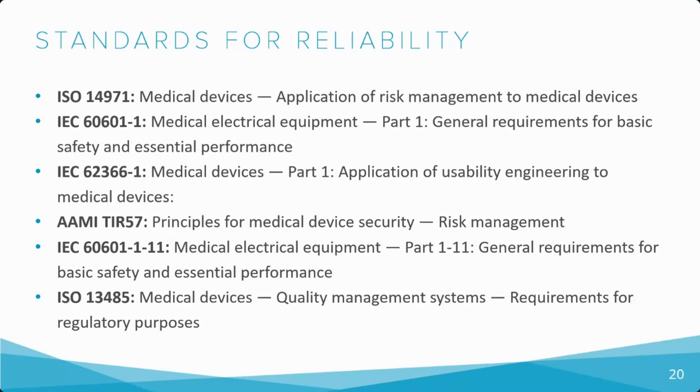ISO 14971 is a comprehensive standard that provides guidelines for managing risk associated with medical devices throughout their lifecycle. IEC 60601-1, this standard outlines general requirements for the safety and performance of medical electrical equipment. IEC 62366-1, usability is an important aspect of reliability. This standard focuses on usability engineering process to ensure that medical devices are designed with user needs in mind and are easy to use, reducing the likelihood of user errors.